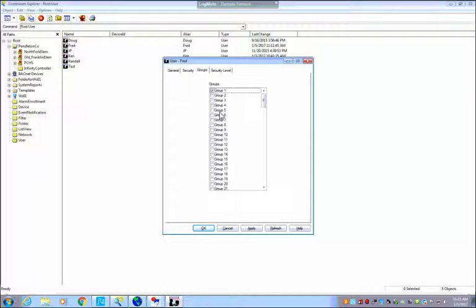I'll show you how to rename these in a minute. But if you give Fred Group 1 and apply it, he now has permission to do anything on this system. He is at an administrative level. He can program, he can configure points, delete points, anything that is possible he can do. And if Fred is qualified to do that, that is a fine option. If Fred is a button-pushing idiot, you don't want to give that to him.